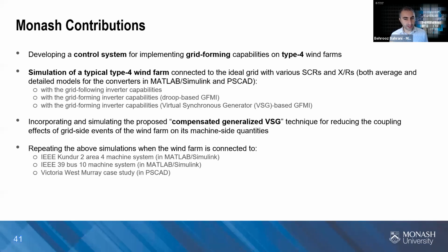We applied that technique as the grid forming capability to see how things would work. And then we are starting now to test it in many different scenarios, larger systems. We started obviously first with the SMIB case. Now we're applying larger systems, IEEE 39 bus, and hopefully the Victorian system, West Murray region, in PSCAD. So we're hoping to apply to those cases and understand how the system would work.